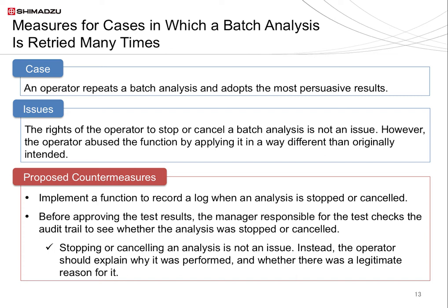However, the ultimate aim of this measure is not just checking the audit trail, since stopping or interrupting an analysis may be warranted. The important question is why the temporary stop took place. A computer system log will only record the fact that a temporary stop was implemented, since computers can only do what we tell them to do. Therefore, you need to question the operator to find out why they performed the temporary stop, and check if their reasoning is valid. The entire process up to this point must be formalized in SOPs, and proper records kept of the operator interview.